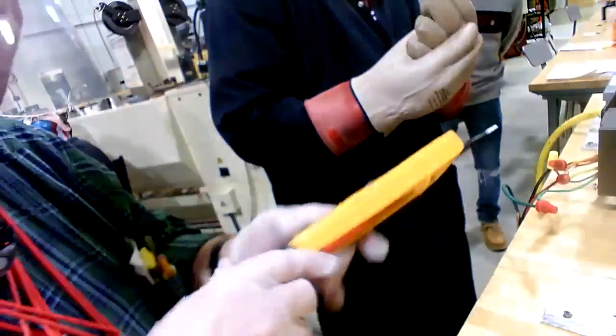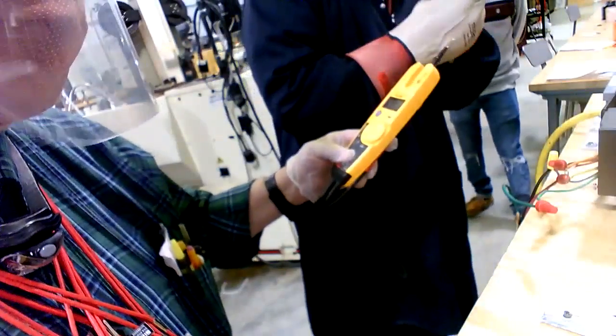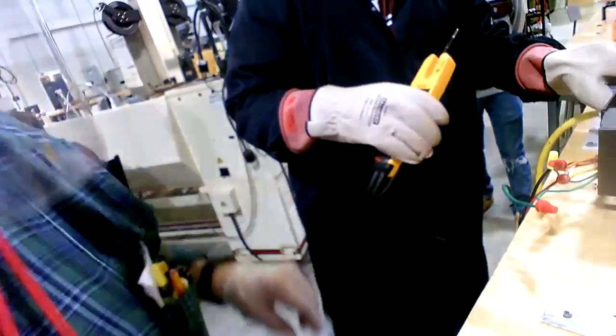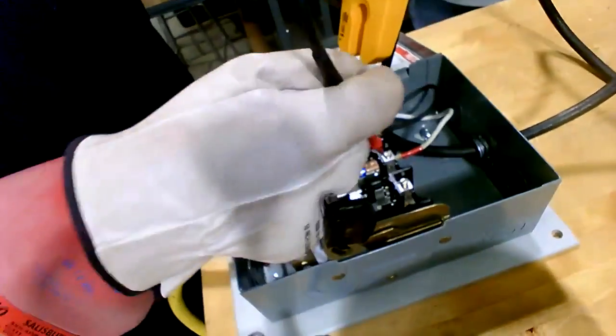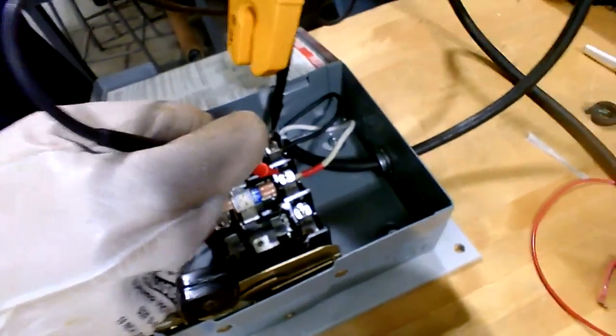Now, so you disconnected it. I want you to verify that the voltage is dead. So before you unhook it, we're going to make sure that it is dead, open that up. And then internally, you'll go from leg to leg and make sure it's zero, and go each leg to ground and make sure it's zero. You're on the volts, okay? Zero there.